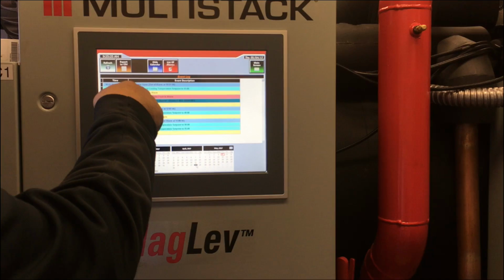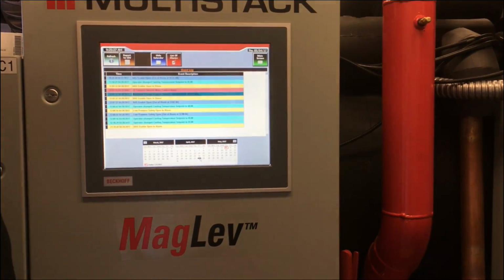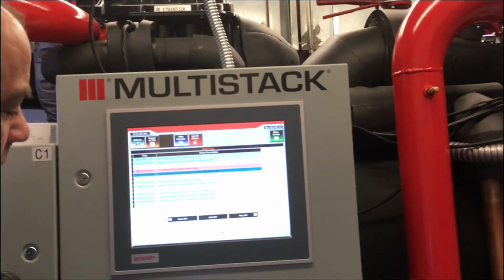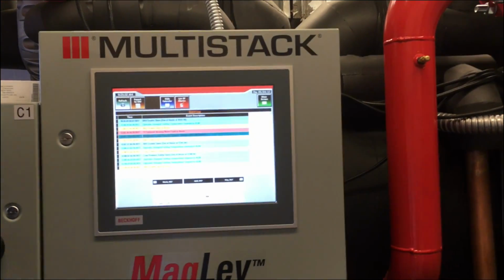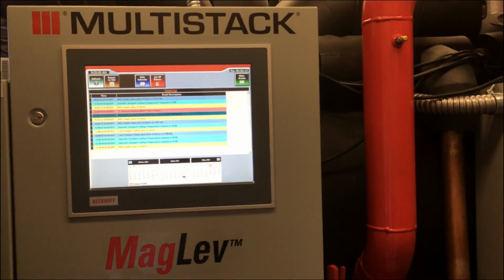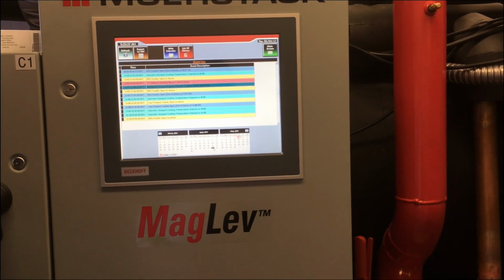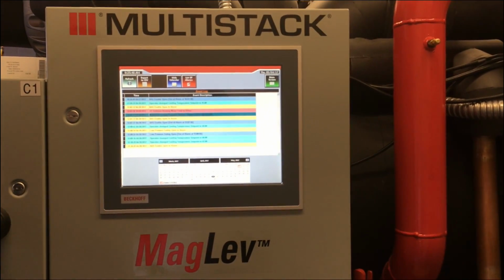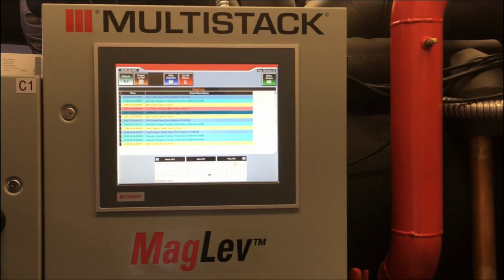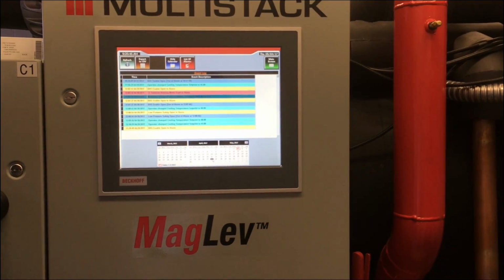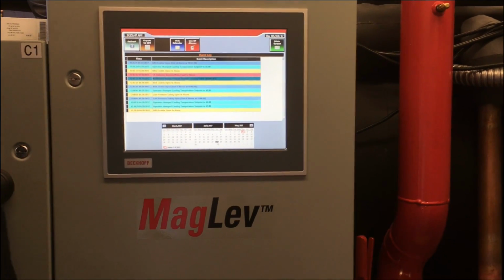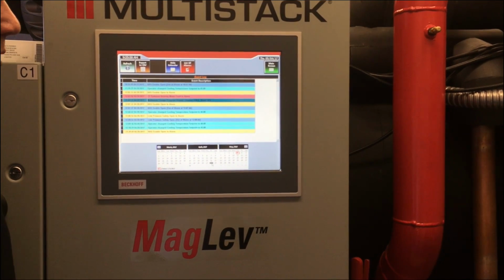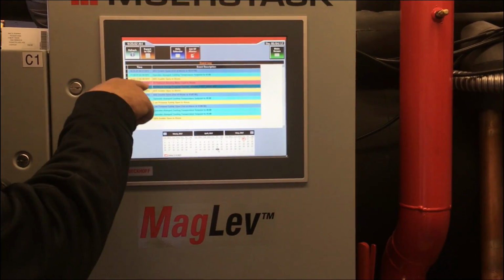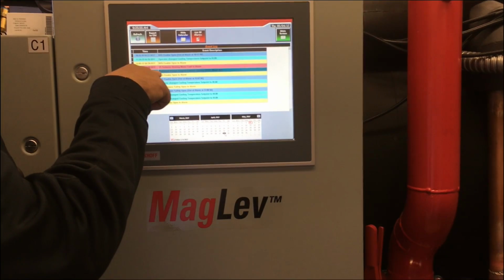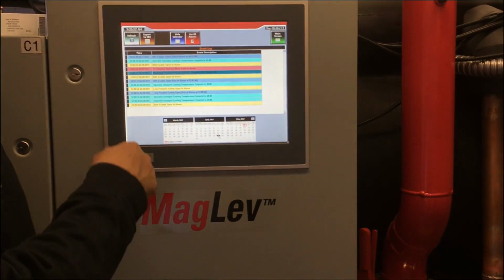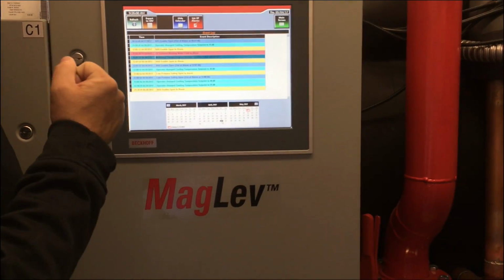And we had a cool, this may even be the day, this can't be the first day I was here. I can't be that lucky. Was it? No, that was just last week. I think we started this 3 weeks ago. Yeah, about that. So it looks like we had a little flow issues because we got some low pressure safeties, open alarm. We have a couple low pressure safeties, so it may have been some water flow things going on, and a Turbocor bearing motor fault, which I'll explain. Oh, that's power down. Because right here we have a Turbocor bearing motor fault, and then right below we have Multistack Flex's program started, which means somebody knocked power down and brought power back up.